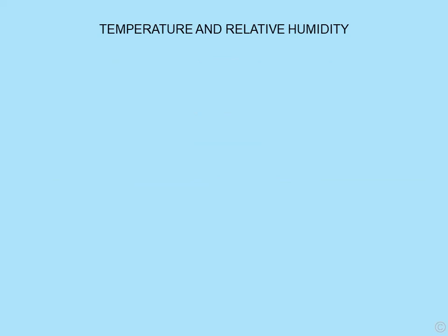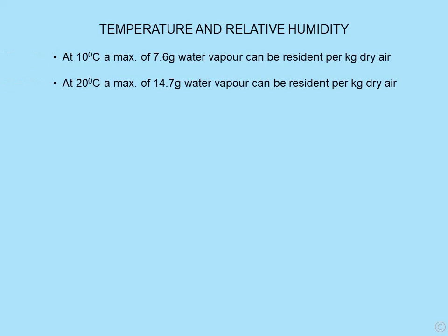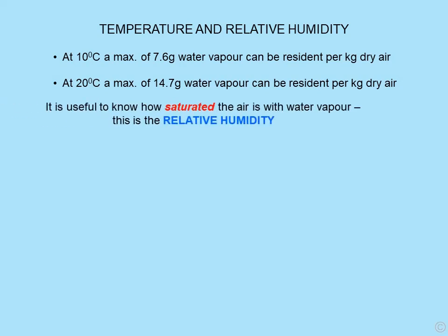Let's first look at temperature and relative humidity. At 10 degrees, seven and a half grams of water vapor can be resident per kilogram of dry air. At 20 degrees — double the temperature — 14.7 grams of water vapor can be resident per kilogram of dry air. So the warmer the air, the more water vapor it can retain. It's very useful to know how saturated the air is with water vapor, and this measure of saturation is known as the relative humidity.